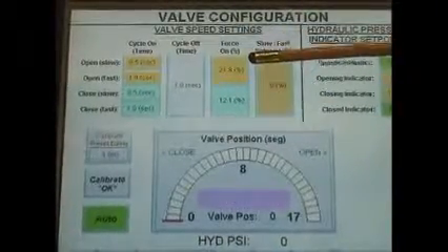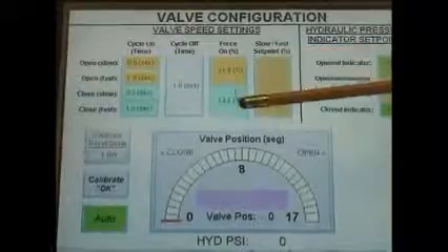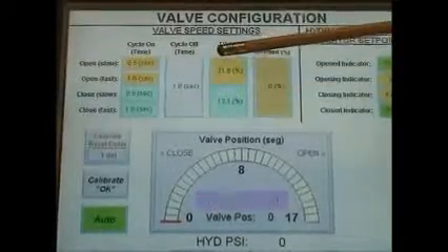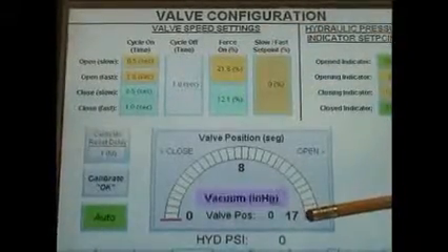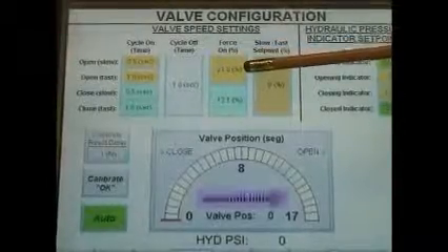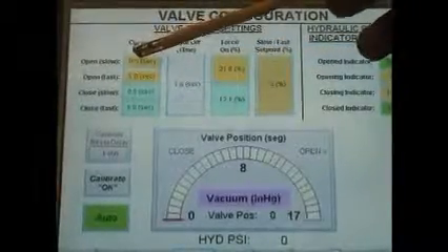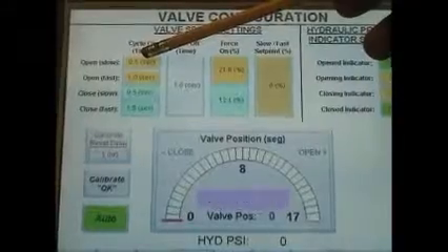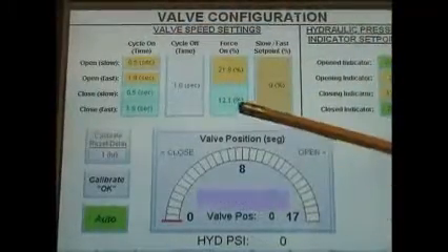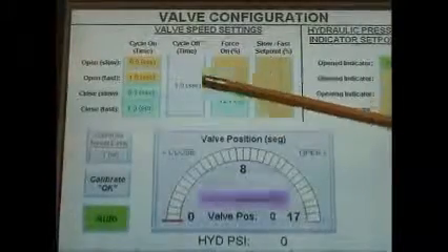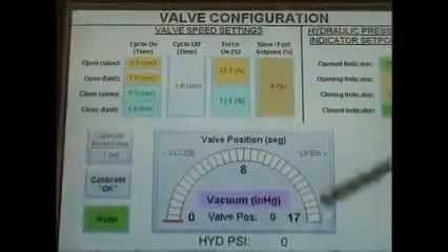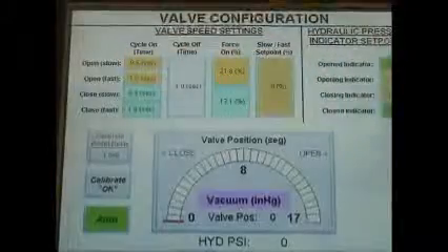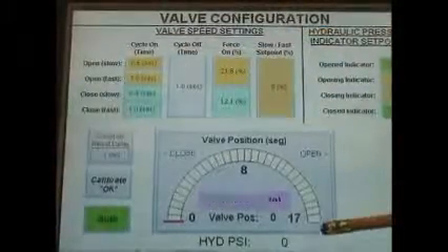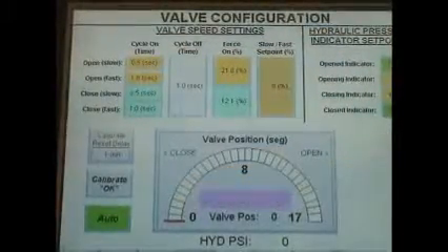So that's where the computer automatically made this calculation, saying if it takes 17 segments to open at 21.8% force for 0.5 seconds each time it tries to open, it's going to have 12.1% force to go closed each half a second, so that we get 17 segments going closed.